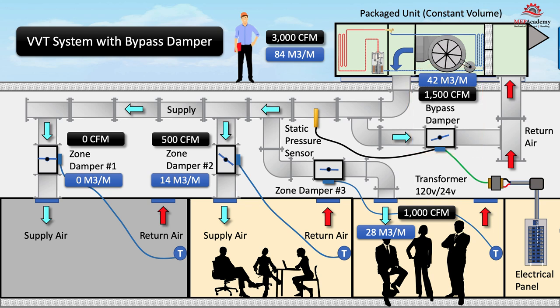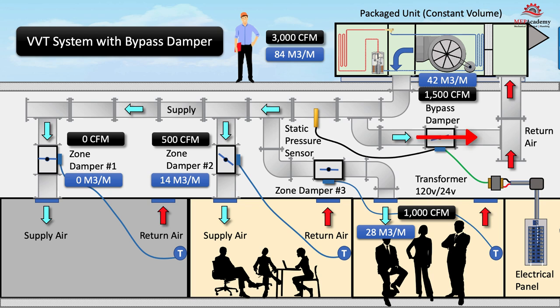Remember that the air conditioner is a constant volume unit and has no way to reduce the air delivered by the unit. This air has to go somewhere, so it is bypassed from the supply air to the return air without entering the space. What happens is that the air becomes cooler or warmer because it hasn't rejected or absorbed heat from the space.